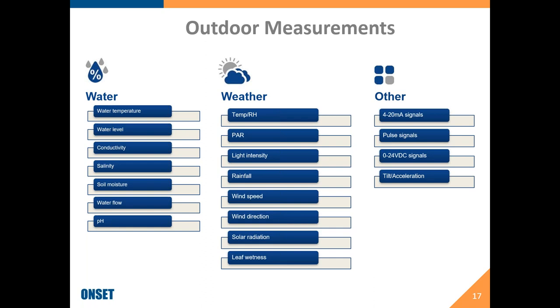On the weather station parameters, we have temperature and relative humidity, PAR — which is for plant light ranges — and light intensity covering solar radiation, which reads in watts per meter squared. It is part of the suite of sensors used for evapotranspiration for agricultural type applications. Rainfall, wind speed and direction, and solar radiation are part of the light intensity suite. Leaf wetness helps in predicting plant disease and would be part of our weather station suite. Other signals include 4 to 20 milliamps — many of our stations can accommodate some third-party sensors. If there's a sensor you need for a particular detail in your application, we can usually accommodate that if it's a 4 to 20 milliamp analog signal. Pulses are typically used with flow meters, and there are voltage signals compatible with a wide variety of equipment.